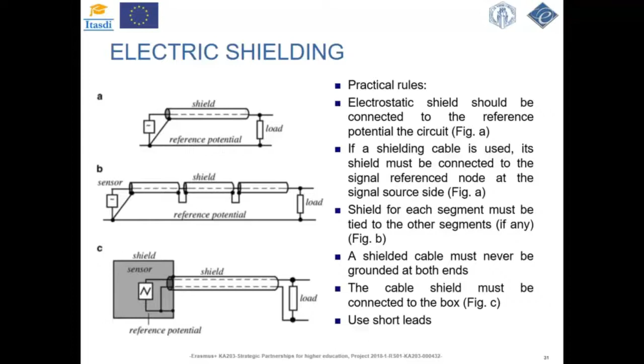And the last rule is that it is advised to use short connection wires to minimize the inductance. This is very important, especially when both analog and digital signals are transmitted into data acquisition systems. So proper shielding can dramatically reduce noise resulting from electrostatic and electrical fields. However, unfortunately, it is much more difficult to shield against magnetic fields because they penetrate conducting materials. A typical shield placed around a conductor and grounded at one end has little effect on the magnetically induced voltage in the conductor. For improving the low-frequency magnetic shielding, a shield made of a high permeability magnetic material should be used. However, the effectiveness of the shield drops at higher frequencies and for stronger magnetic fields.